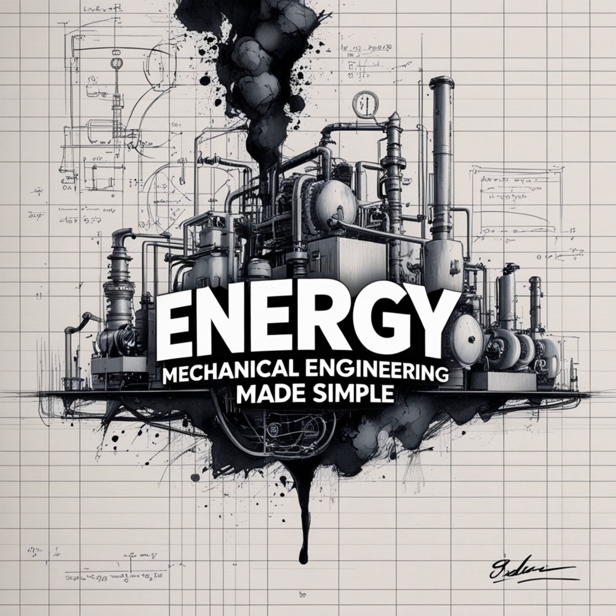Wow. Okay, so you have the basic conduction resistance, the spreading resistance, the contact resistance. How do we sum this all up for, say, a whole chip package? We use an overall figure of merit. The total thermal resistance, R sub T, it's usually defined empirically. Empirically meaning based on measurement. Yeah. R sub T equals T sub J minus T sub FL, divided by Q sub C. So the junction temperature, T sub J, minus the coolant fluid temperature, T sub FL, all divided by the chip's heat output, Q sub C, basically degrees C rise per watt. Exactly. It tells you the total temperature penalty for getting heat from the junction out to the coolant.